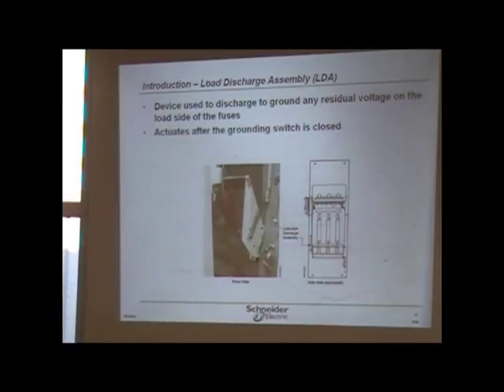The 3 positions, ooh, excuse me. This is the discharge assembly, and it showed where it goes down over here, once it opens up, discharges and grounds any residual voltage on the load side of the fuse. And of course, like I said, it's actuated by the grounding switch being closed.